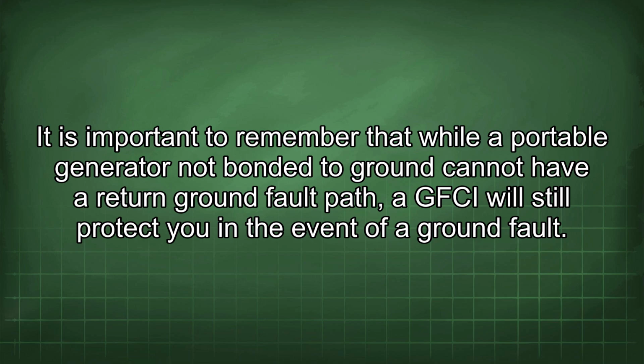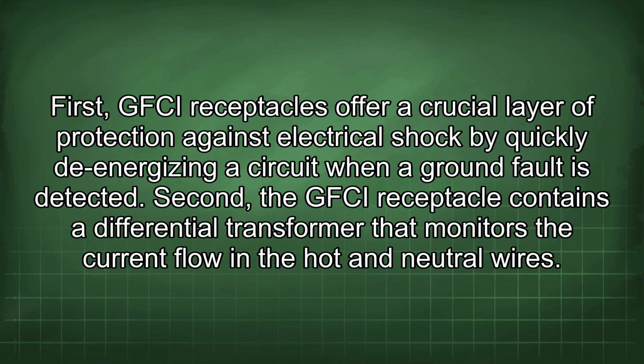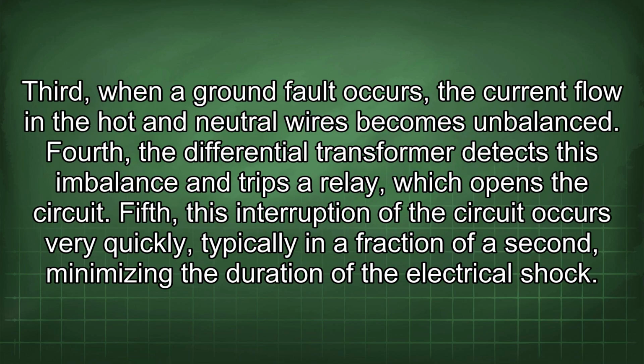It is important to remember that while a portable generator not bonded to ground cannot have a return ground fault path, a GFCI will still protect you in the event of a ground fault. First, GFCI receptacles offer a crucial layer of protection against electrical shock by quickly de-energizing a circuit when a ground fault is detected. Second, the GFCI receptacle contains a differential transformer that monitors the current flow in the hot and neutral wires. Third, when a ground fault occurs, the current flow in the hot and neutral wires becomes unbalanced. Fourth, the differential transformer detects this imbalance and trips a relay, which opens the circuit.